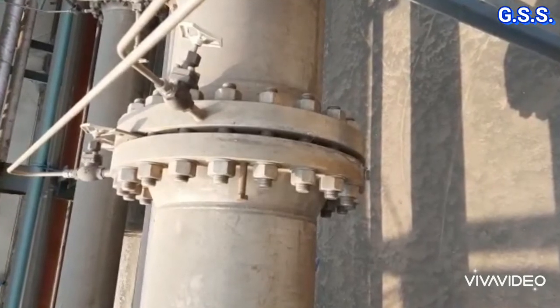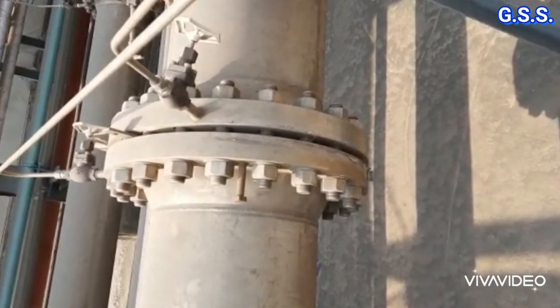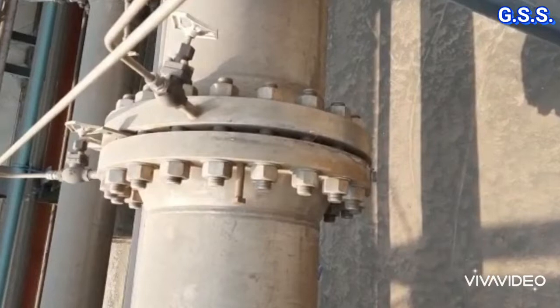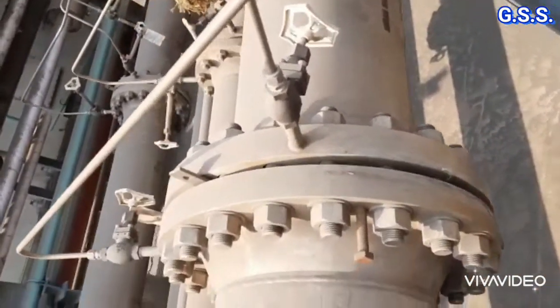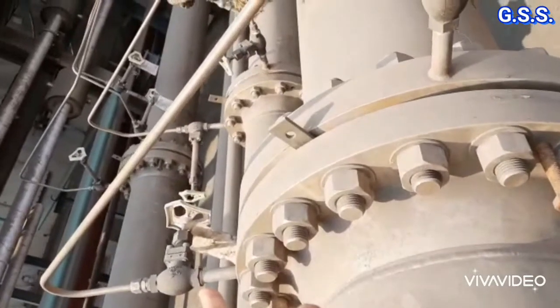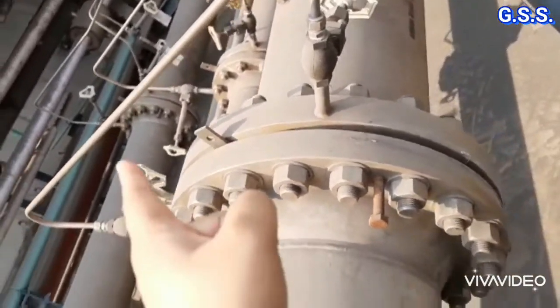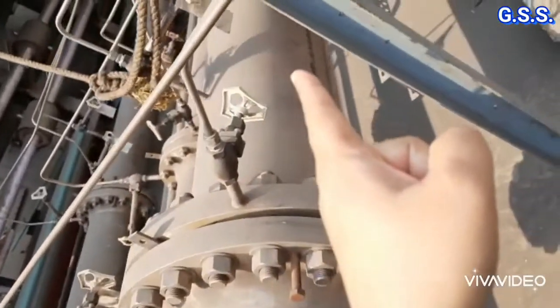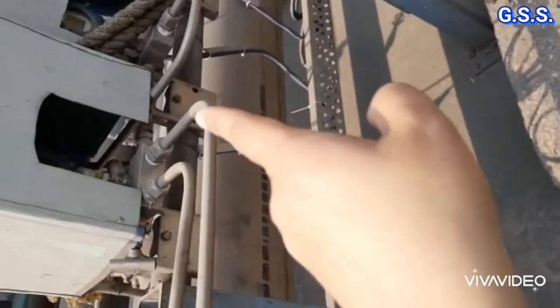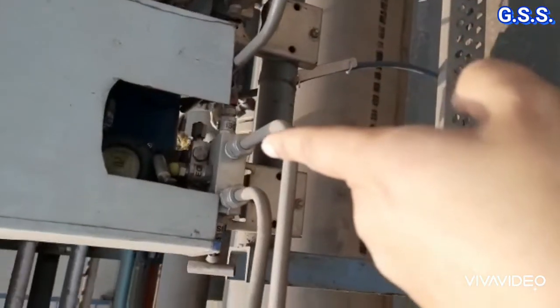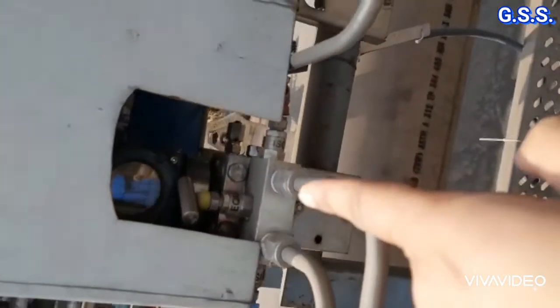This is an installation of an orifice between two orifice flanges. Two half-inch tappings with root valves are provided on the orifice flange across the orifice. From the root valve, tubing goes to the transmitter, which measures the flow based on differential pressure across the orifice.